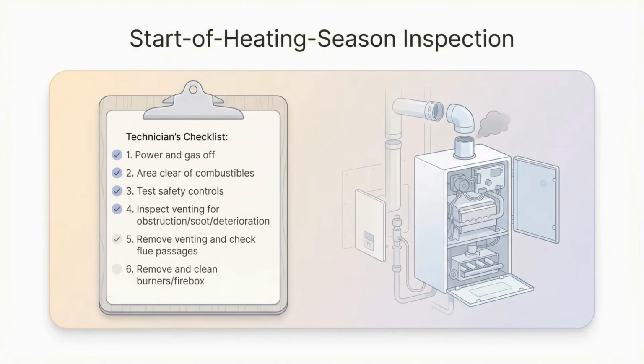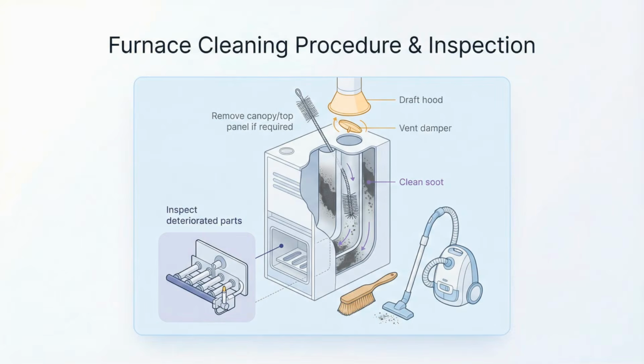Then confirm the area is free of combustibles and flammable vapors. Check safety controls, inspect venting for blockage and deterioration, clean flue passages as needed, and remove and clean burners and the firebox, typically with a vacuum and soft brush. Many boilers need access panels, or even the jacket top or canopy, removed to clean properly. The goal is to remove soot and blockages from the flue passages and ensure the venting path is clear.